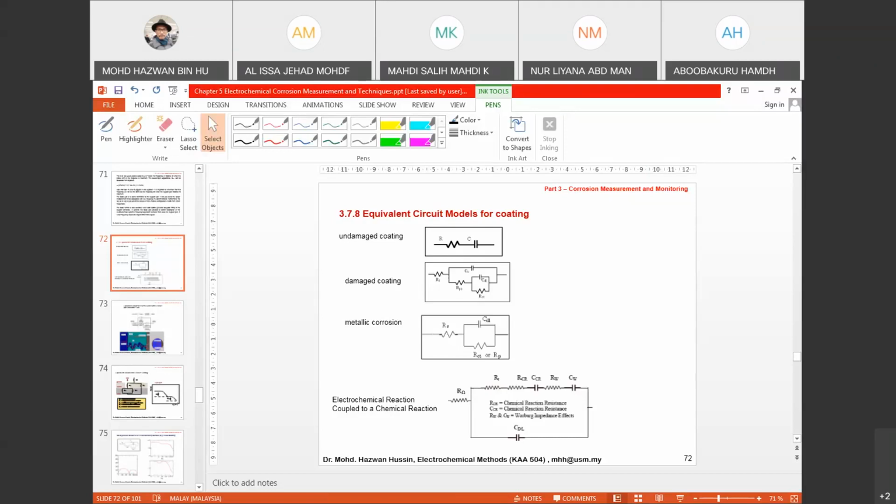But in the case of a solid state sample, like if you want to check the conductivity of your solid material, you can use impedance because it can measure the resistance, and from the resistance you can calculate conductivity. With this one, you will not have resistance of solution, but you will observe that it forms a 45 degree line, and this is actually due to diffusion. So it depends on the sample.